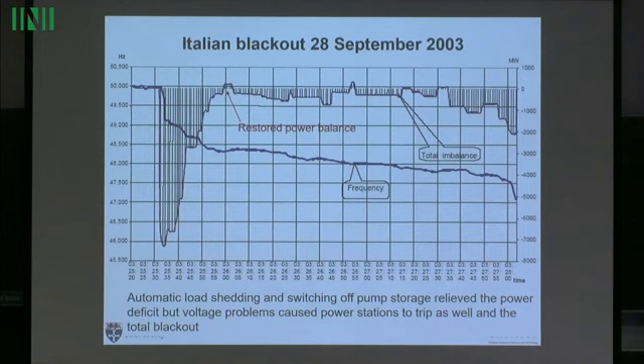So first they disconnected pump storage. Italy has a lot of mountains, so they have a lot of pump storage, and this happened during the night - during the night you pump water up and let it go during the day. So when the frequency dropped, the first thing they did was stop those pump storage plants which were working all the time. As you can see, the deficit first decreased, but because it dropped further in hertz...